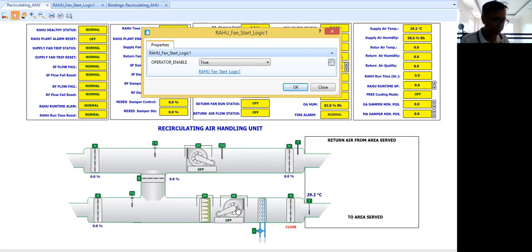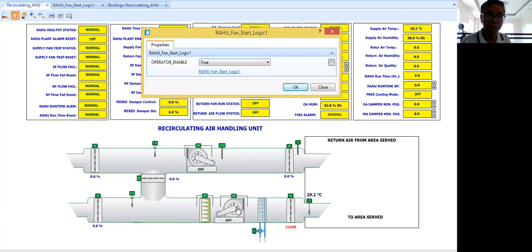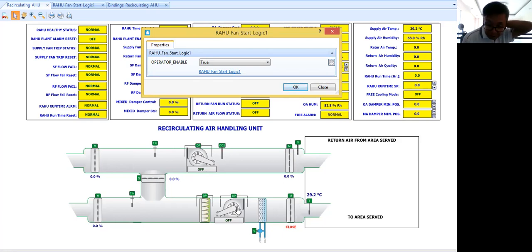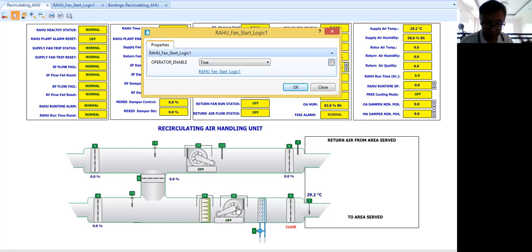Now the idea for that one is you don't want to create, even though maybe you are implementing soft starting Wye Delta or you have a VFD for this, even though you have soft starting, you don't want to start these two big fans at the same time because you don't want to create a sudden voltage drop.